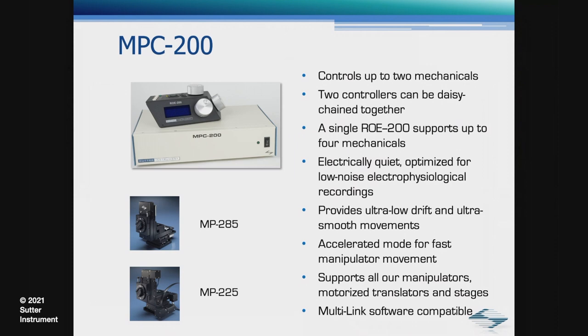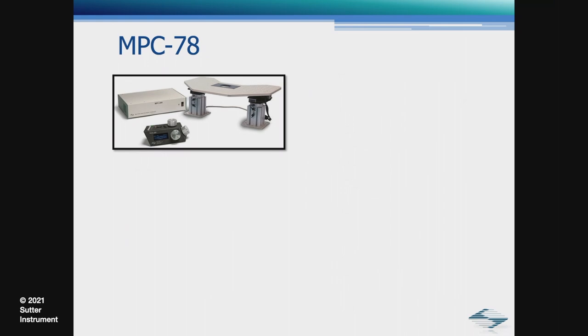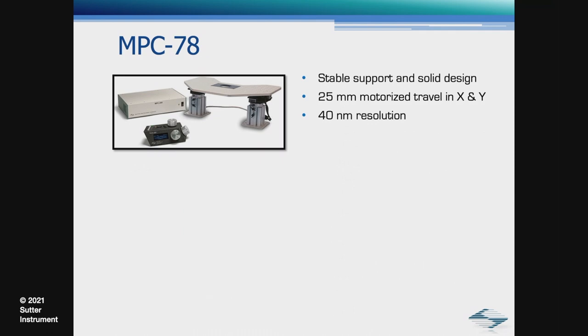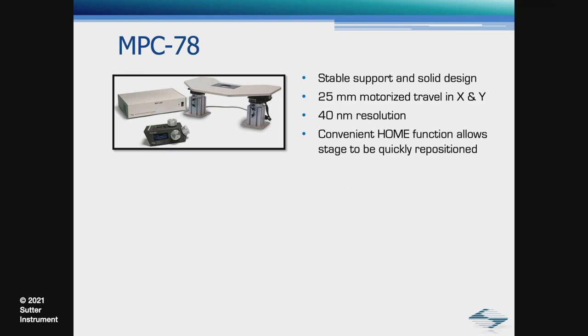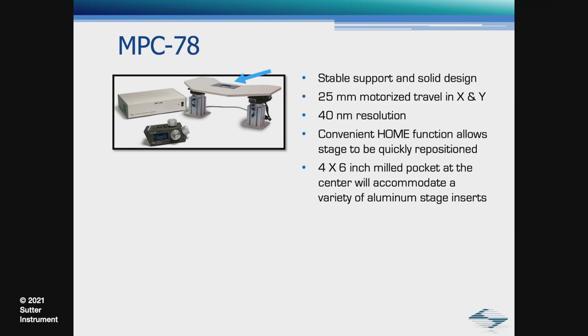Next, we have the MPC-78 stage. Features include stable support and solid design, 25-millimeter motorized travel in both X and Y. The MPC 200 controller provides 40-nanometer resolution steps. Convenient home function allows stage to be quickly repositioned. 4-by-6 milled pocket at the center will accommodate a variety of aluminum stage inserts. We also have custom aluminum inserts available.